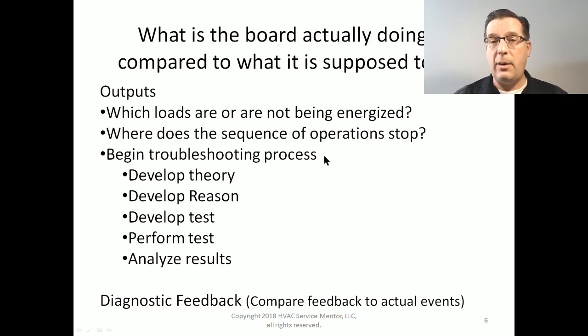Remember that the sequence of operations is not all go time. Sometimes the sequence of operations says stop. That could be an example of something going on that means it's not safe to operate right now, and the control board could be responding to that. That is why so many electronic circuit boards get replaced when there's nothing wrong with them. What is discovered later is that either they were never getting the input, the operating command, or there was an external situation it was responding to, saying, hey, it's not safe to run right now, I'm not going to, or I'm not able to for some reason. That means we're not only troubleshooting the circuit board, we're troubleshooting the holistic machine, which is controlled by this circuit board.